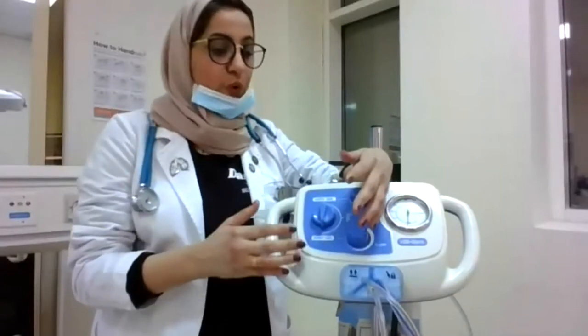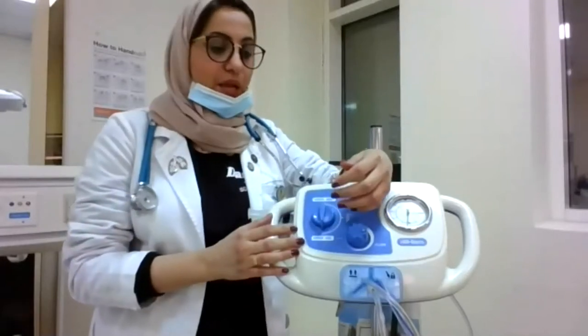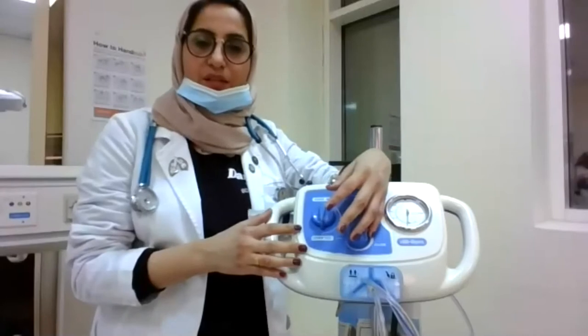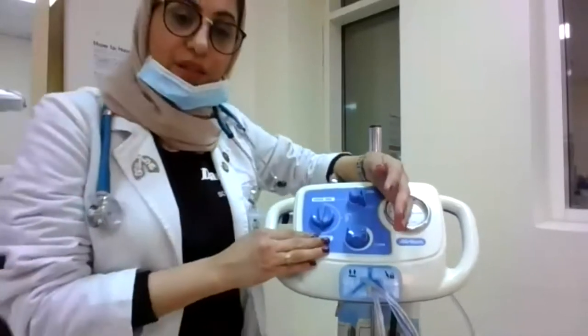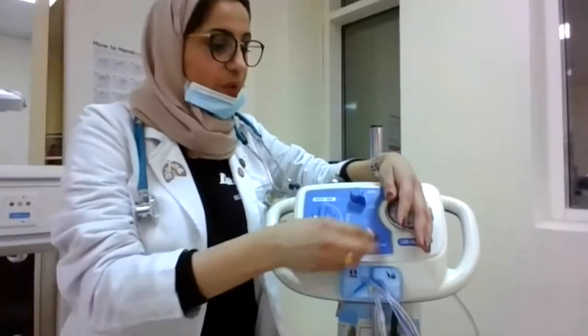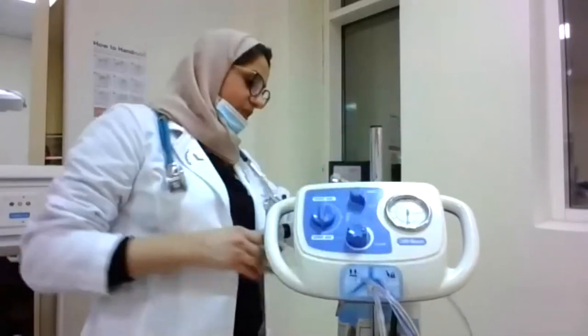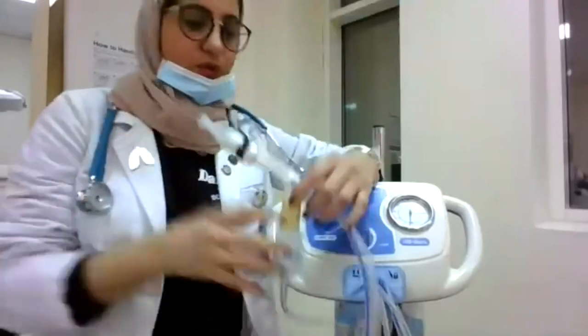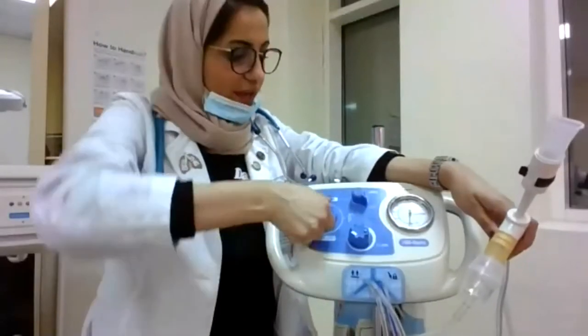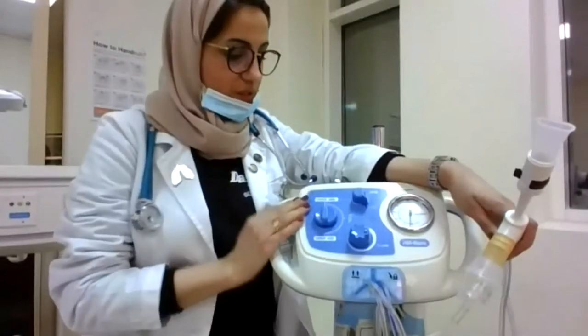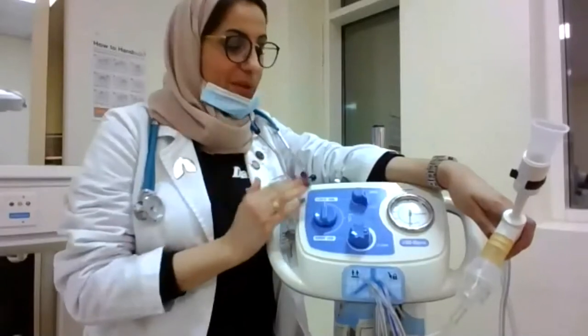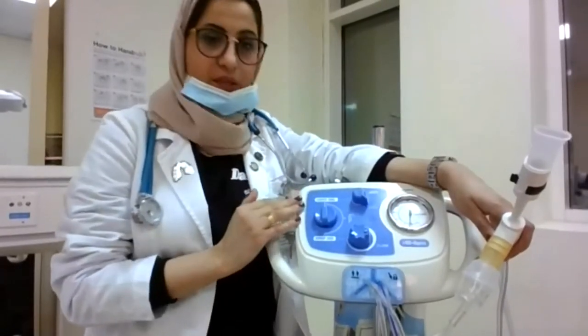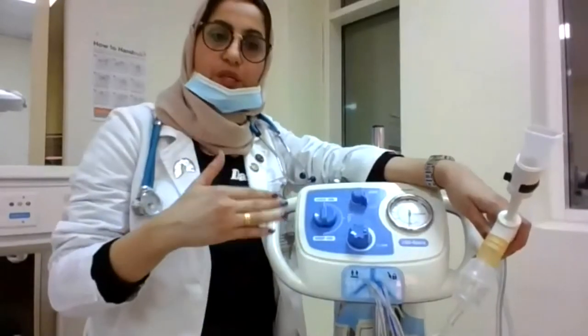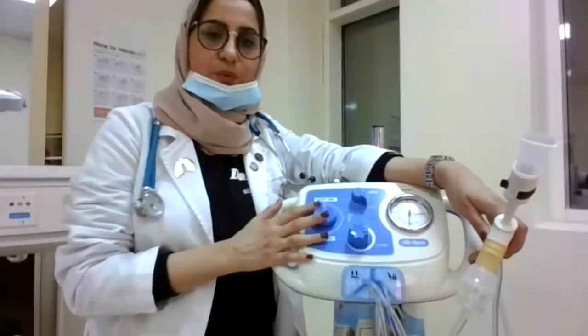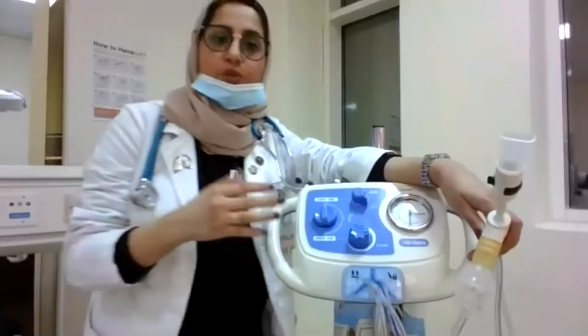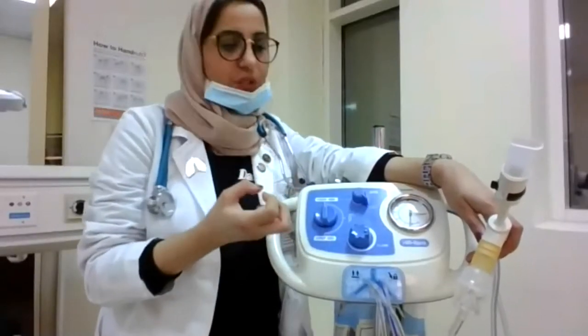This flow will move beyond the secretion that is retained in the airway, and it will help in secretion mobilization and reduce air trapping. The flow in this mode will be adjusted by the clinician, and we will go up and down with the flow until we see the medication getting aerosolized out of the mouthpiece. The second mode in this device is the continuous high frequency oscillations mode. It's a combination of the aerosol medication and continuous high frequency oscillation, where it will form a continuous pulse of positive pressure while the patient is taking their aerosol medication to help in loosening up the secretions.